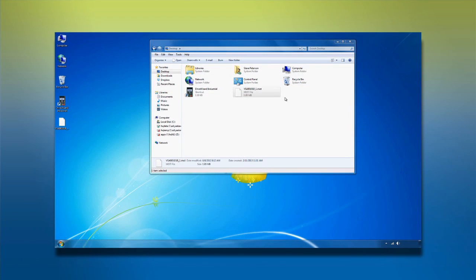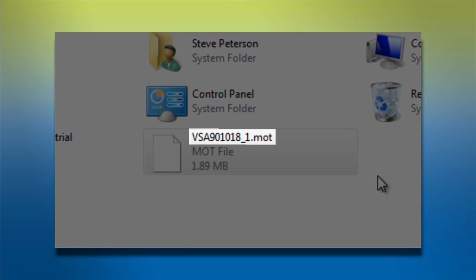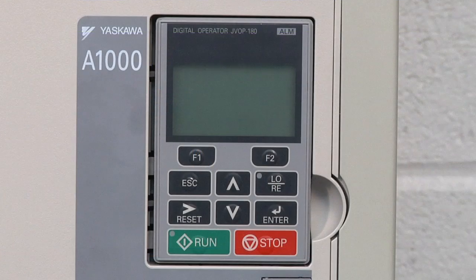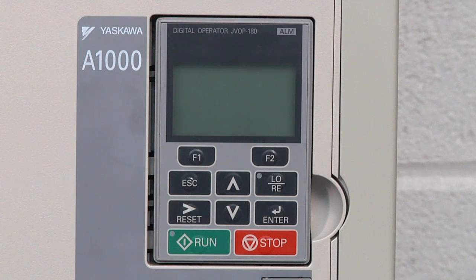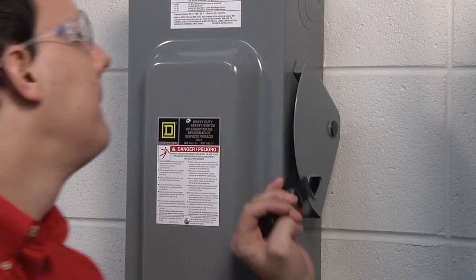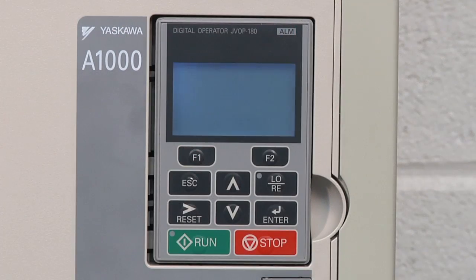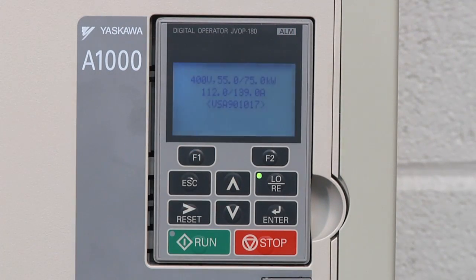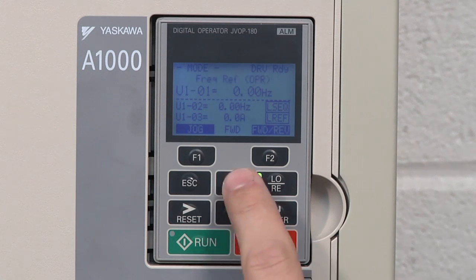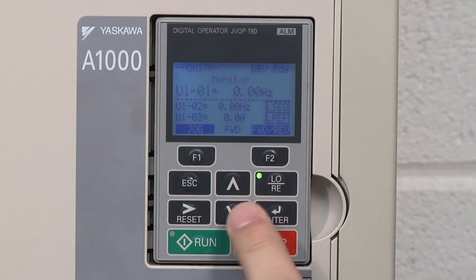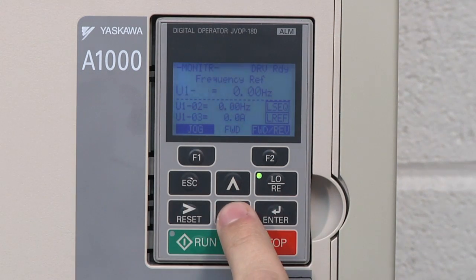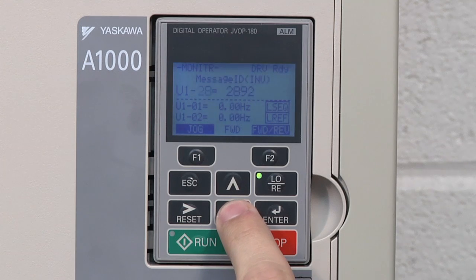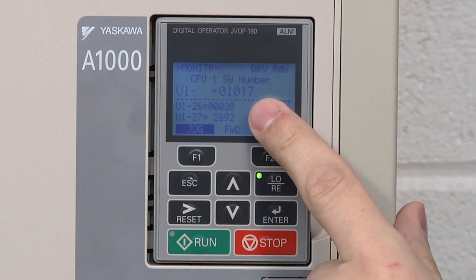Now that you know the most current flash file version, you'll want to compare it to the version of the flash file that is currently on the drive. And you can do this by using the LCD display on the drive that we're seeking to update. Begin by powering up the drive. Then, using the keypad to access the monitor menu and selecting the monitor U1-25. This will tell you the version of the file currently resident in the firmware.